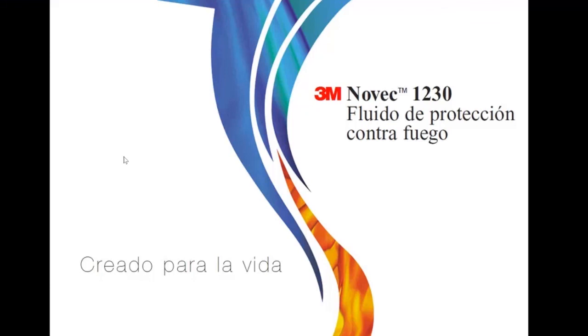So when overheat happens, obviously because of a fire, this red line is a hose pressurized with nitrogen. It opens in the part that overheats, letting the pressure go down, and that's the signal that brings the cylinder to the discharge process.